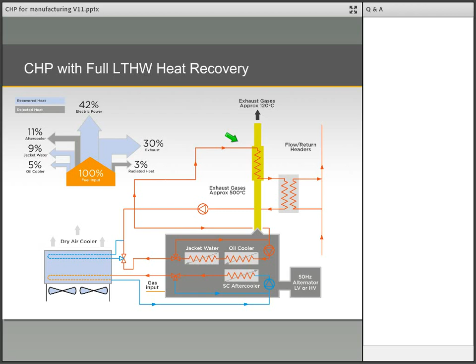In most modern gas engines there is a 2-stage aftercooler, with the first stage being high temperature and circuited in with the engine water jacket circuit. In these cases, up to 88% of the energy being put into the system can be recovered as power and LTHW. This can further be enhanced if a use can be found for the lower grade stage 2 aftercooler heat.